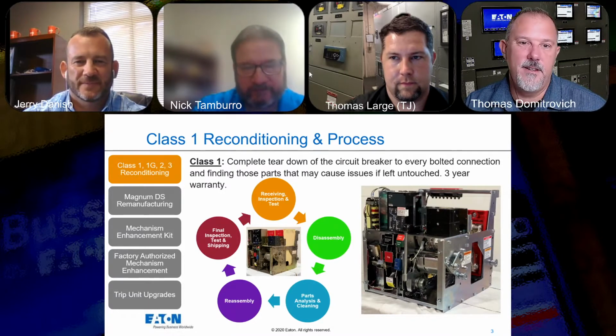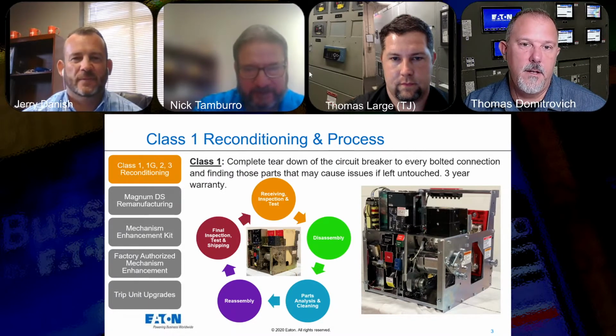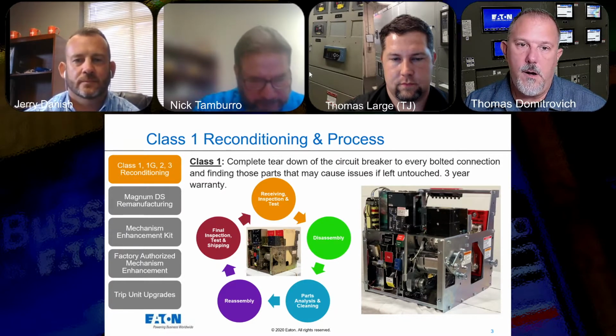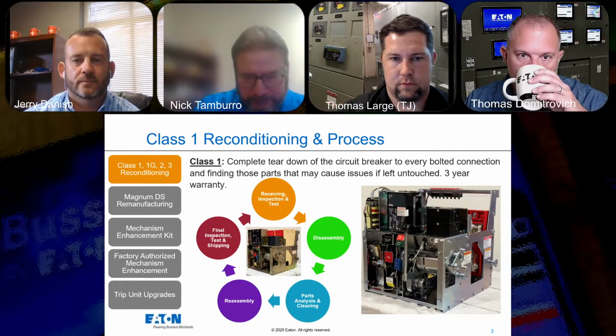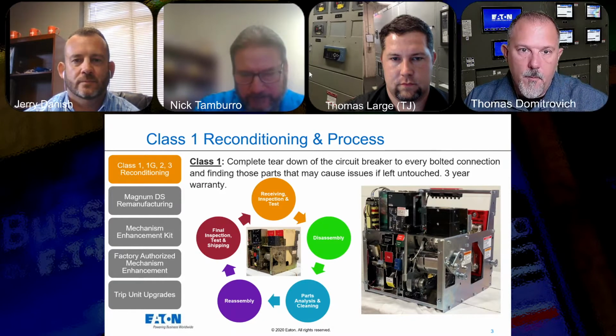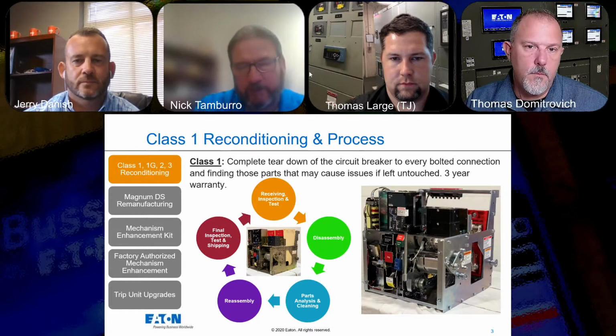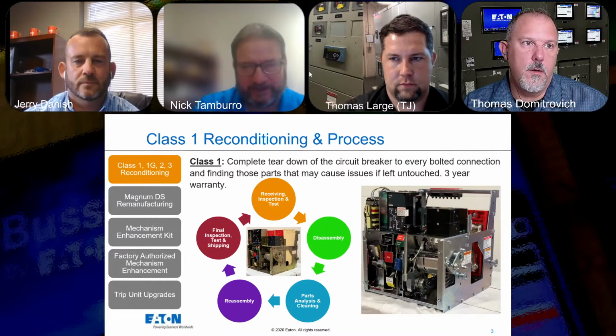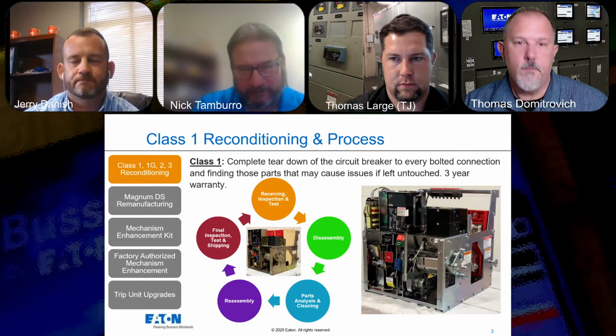So when we receive a breaker, the first thing we do is test it. If it's electrically operated, we'll operate it 5 times at min and max for the open, charge, and close. We also do incoming primary injection testing if you're retaining that trip system. But if you're retrofitting it, there's no benefit to testing the old one.